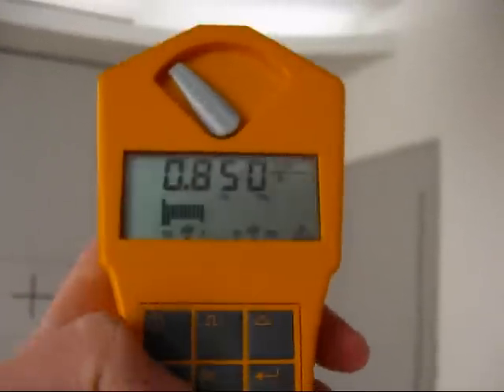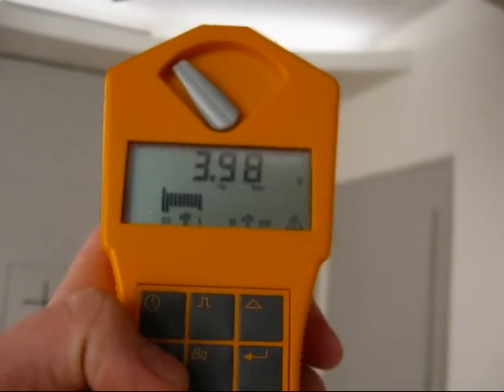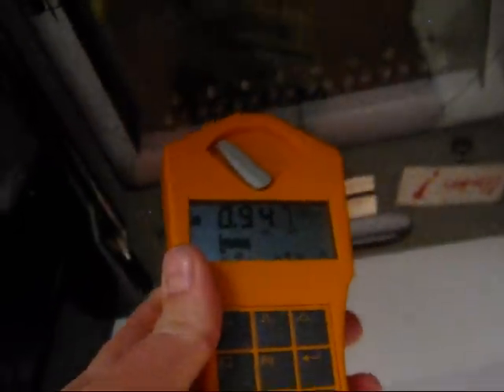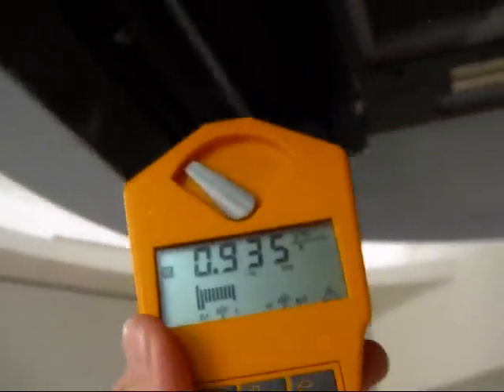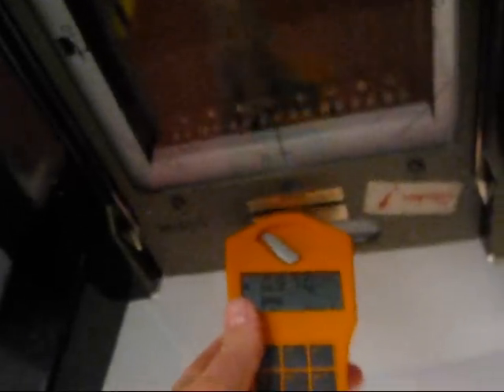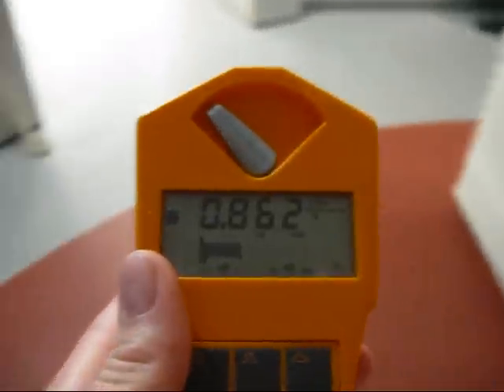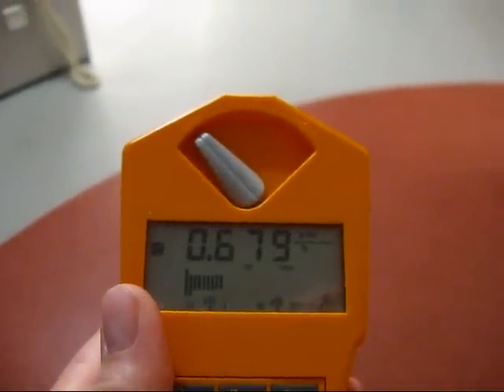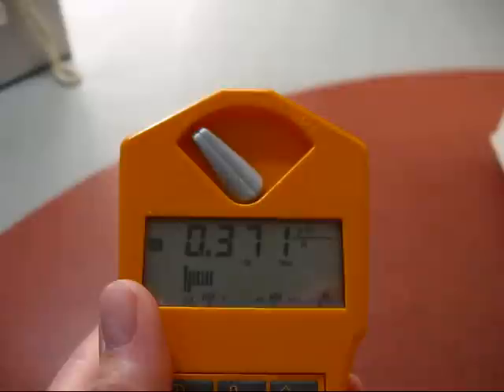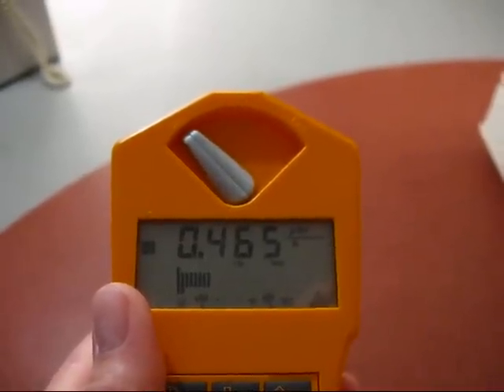Let's see. Fetching my Gamma Scout. Now you can see, still high background radiation here. I'm measuring the head of the linear accelerator, which previously was not radioactive. You'll just have to trust me on that, but of course I measured it. I just didn't record it. And you can see, the head of the linear accelerator is radioactive, but so is the Gamma Scout. When I fetched the Gamma Scout, I didn't record that bit. But you can see, if I hold the Gamma Scout away from the linear accelerator, it will still read an increased background radiation reading. And it does so even when out of this room.